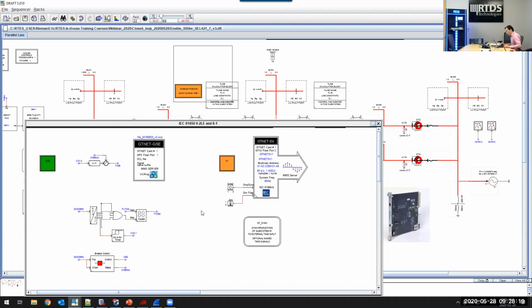Let's move on to the GOOSE interface here. This is the GTNet GSE component. The main function of the GTNet GSE in this demo is to send breaker status to the external relay and receive trip and reclose control signals from the external relay using the IEC 61850 GOOSE protocol.